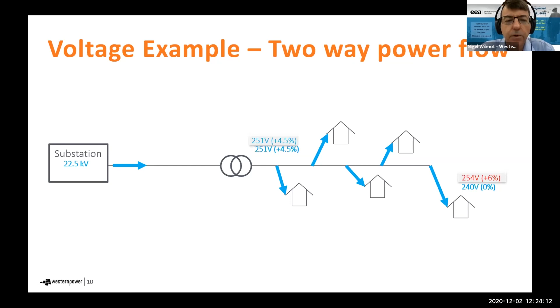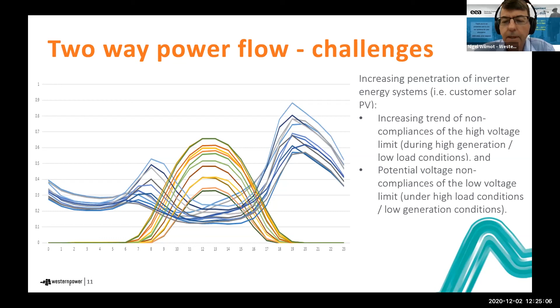As you can see, I did mention earlier about the two-way power flow. The middle of the day load is being eaten out in the centre of the day by the ever increasing solar curve. And unlike South Australia, who can depend on their neighbours to provide frequency, a 100% renewable supply is a challenge that Western Australia will need to deal with, as we still need synchronous generators to provide system inertia, provide system stability and keep our grid afloat.